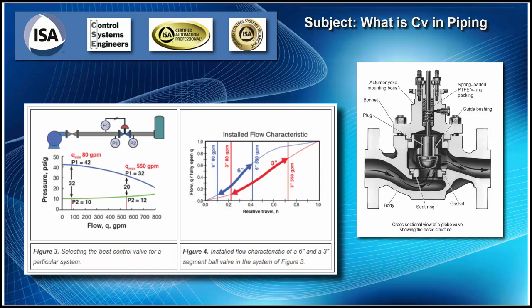So remember, you can use 100% of the valve if you have the delta P, if you've calculated for that amount of delta P, and it's in the system. But most installations have a normal operating range, and then you're trying to correct for upsets. As you speed up, you'll tend to run out of differential pressure. You'll tend to choke and run out of differential pressure as you speed up for an upset. So be careful. If we were sizing a valve for a real plant, we'd probably have an operating flow of, say, 800 gallons per minute. Then we'd want to increase 20% and go below 20% for upsets. So we'd have a high flow, a low flow, and a normal operating condition.